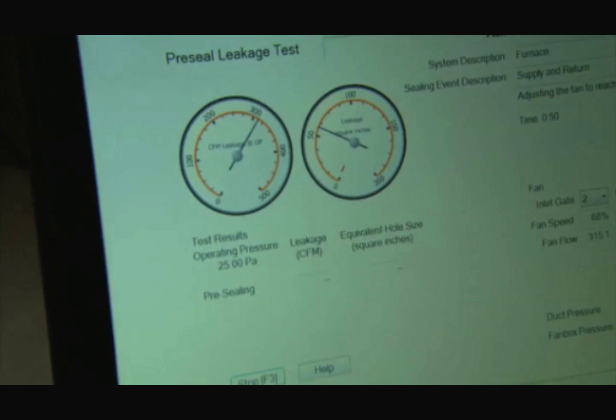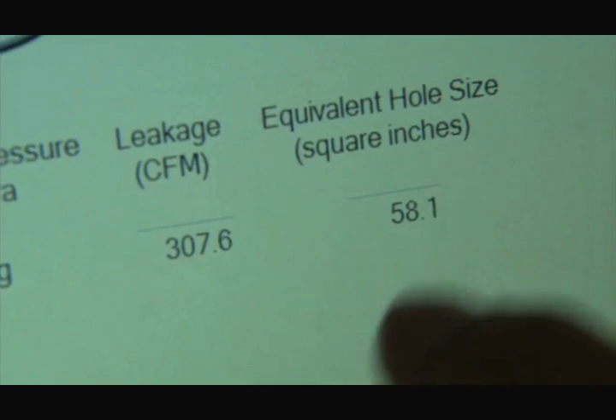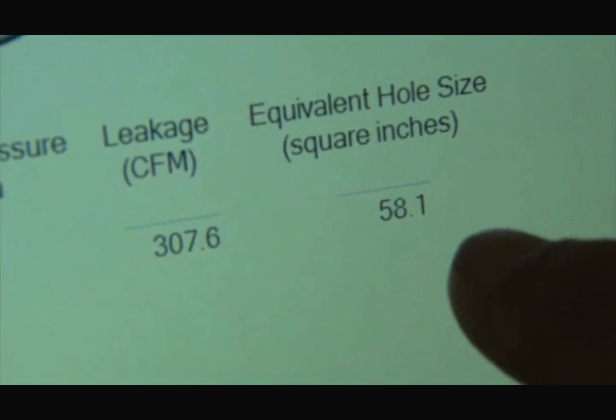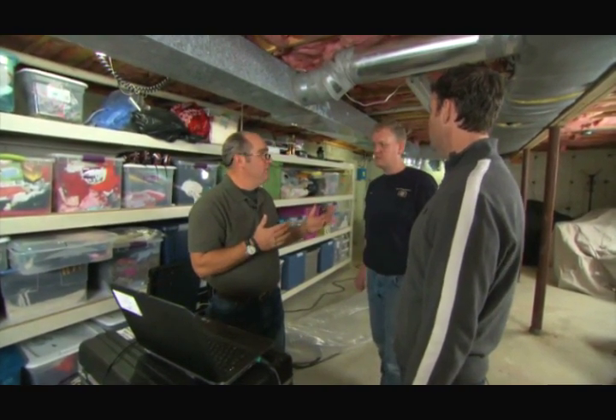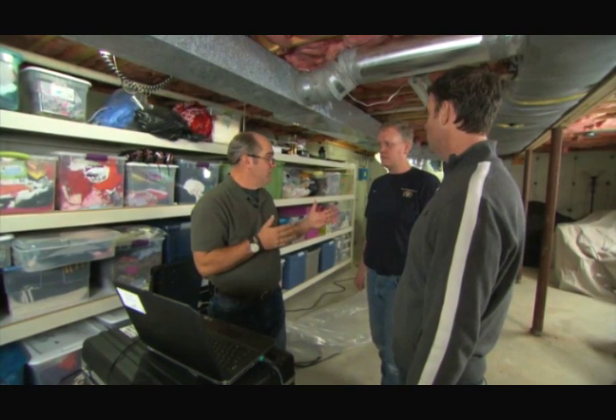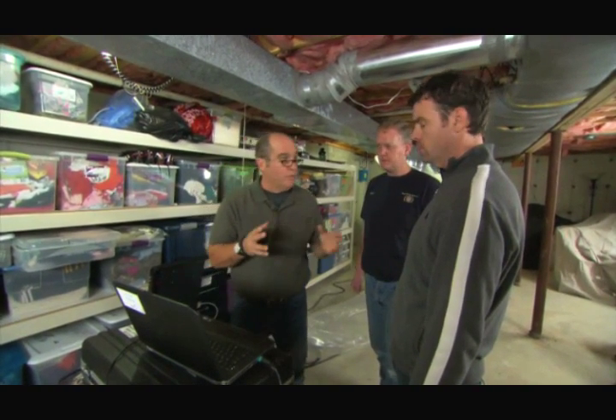All right, so how did we do? We lost 307 CFM, cubic feet per minute, and that's equivalent to a hole in your ductwork of about 58 square inches. That's a big hole. Wow. So let's do the math. 307 CFM, this is a 4-ton system. That's like just under 20%, right? Correct. Okay. So 20% is not coming back to be reheated. You're heating your neighbor's house.